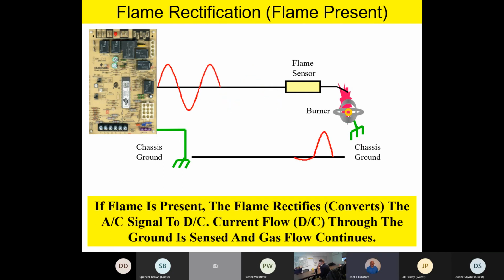However, when you start a fire, so to speak, that AC voltage goes through the flame sensor and through the flame itself to the burner. Now, the burner is grounded on chassis ground, and the control board is also grounded on chassis ground. So that AC voltage goes through the sensor, through the flame, and then it's rectified. The flame itself actually acts like a rectifier. What it does is cut that voltage in half. Now, it isn't a perfect circuit. That's what they call a poor rectifier.